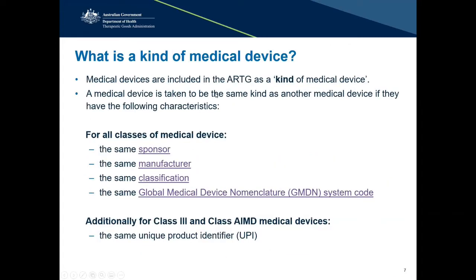And medical devices are included in the ARTG as a kind of medical device. And so a medical device is taken to be the same kind as another medical device if they have the same sponsor, manufacturer, classification, and GMDN code.